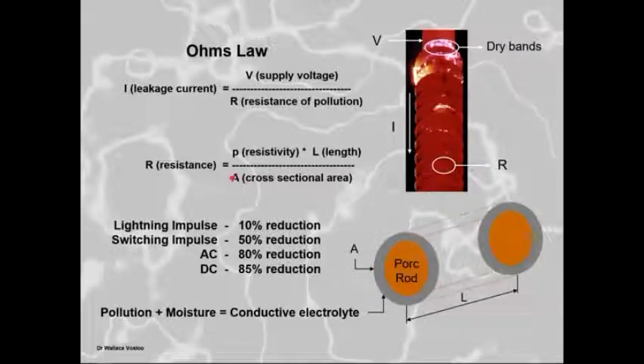Divided by the cross-sectional area available for current flow. So you've got a porcelain rod in the center, the area around it available for pollution and current flow, and then you've got your length L, which is your creepage distance. So if you have your pollution plus your moisture, the conductive electrolyte, and you change the area or change any of these, you change that. Just as interest, if you have an insulator that's polluted, that pollution only reduces the lightning impulse performance by about 10%. Switching, because it's there for a longer period of time, is about a 50% reduction in the level, but you can see here for pollution, for AC and DC, big problems, okay?